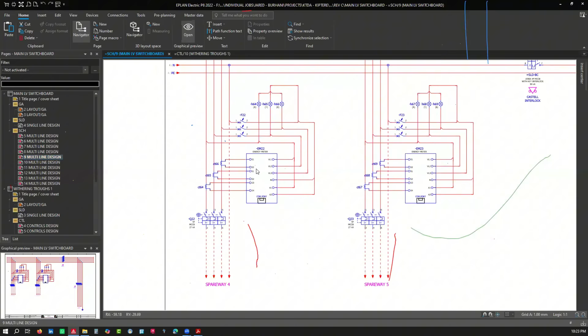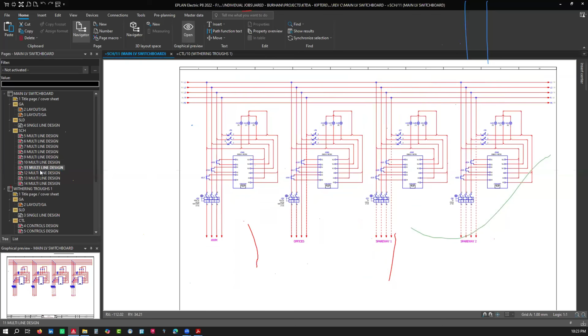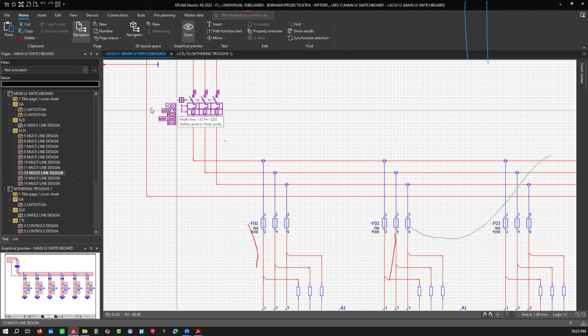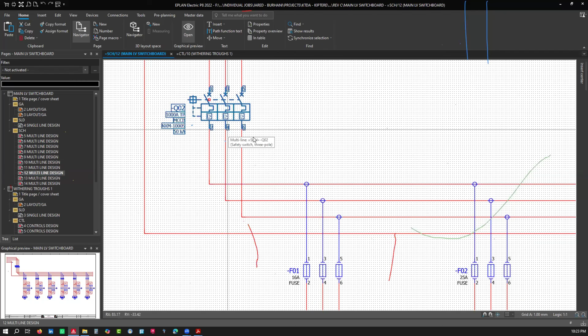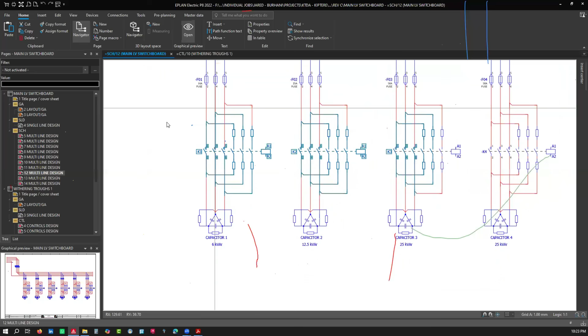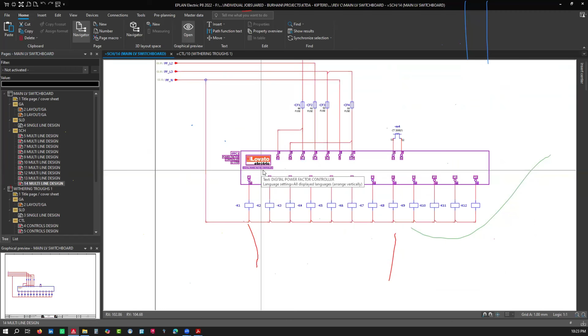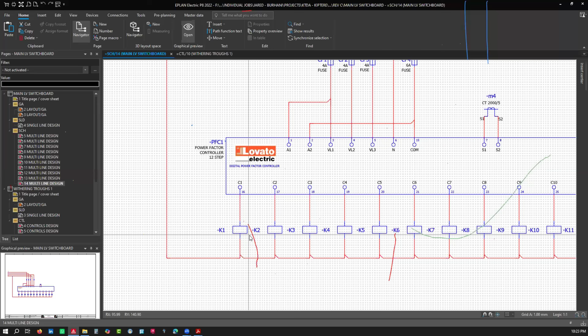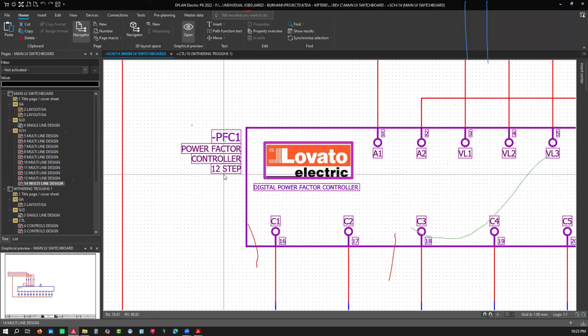Then you go further - remember the power factor. In the multi-line, I've represented my power factor starting from the main breaker to the described capacitor banks. We have the steps plus the capacitor contactor plus the protection breaker, and then I need to come up with the power factor controller. You need to develop the system.